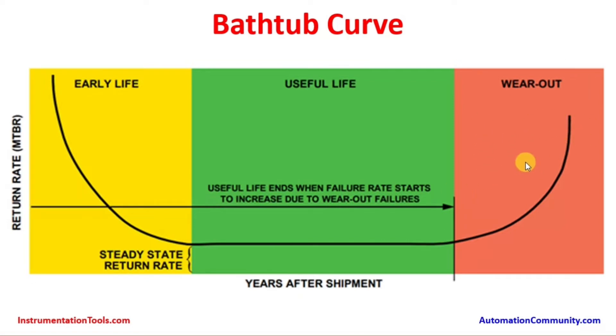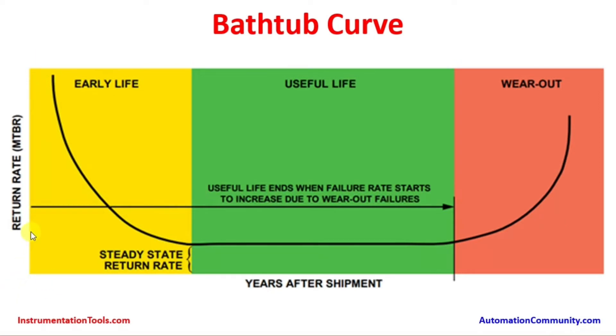In the yellow and red zones the probability of failure is quite high, while in the green zone the instrument operates healthily and effectively for many years. The x-axis represents years after shipment and the y-axis represents return rate, or mean time between repairs (MTBR). The shape of this curve resembles a bathtub — hence it is called the bathtub curve. This is applicable for all instruments and specifically for safety instrumented systems.